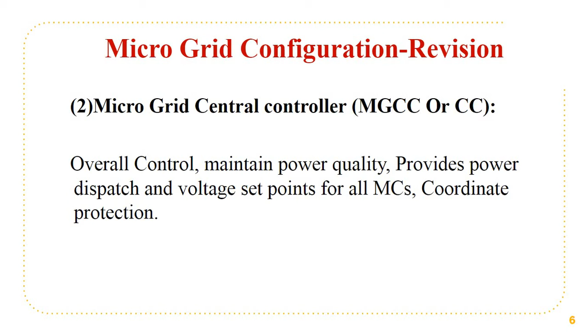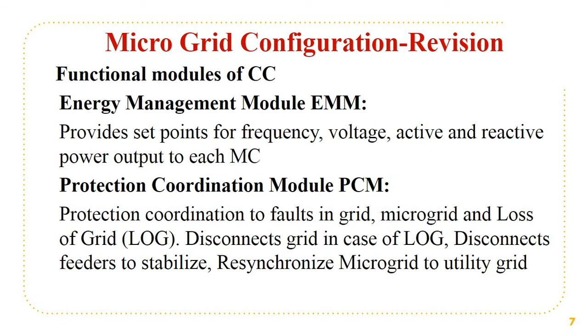The energy management module provides set points for frequency, voltage, active and reactive power output to each microsource controller. The protection coordination module is responsible for acting on the protection devices whenever a fault occurs in the grid or in the microgrid, and on loss of grid. It disconnects the grid in the case of loss of grid, LOG, disconnects feeders to stabilize the power, and resynchronizes the microgrid to the utility grid whenever the microgrid is connected to the grid.